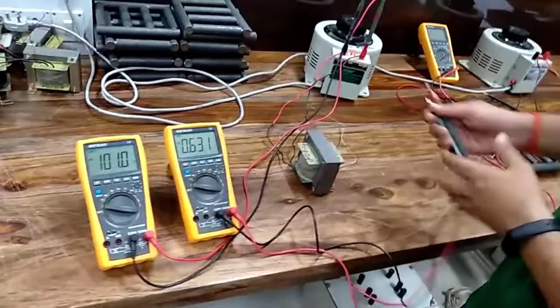Now we are going to test the polarity of the transformer. We will make one connection between these two windings and one connection between these two windings. When the flux is in a similar direction, we get an additive voltage, while when the fluxes are in opposite directions, we get zero or nearly zero voltage. So we have connected the primary to the transformer and we are getting 100 volts. Now we have to take this to 230 volts.